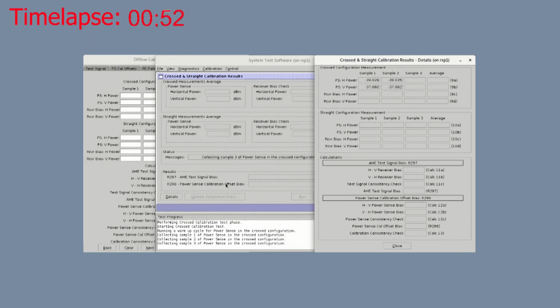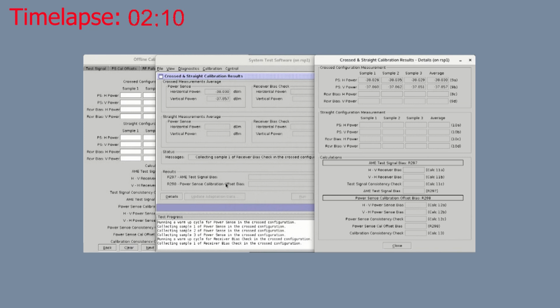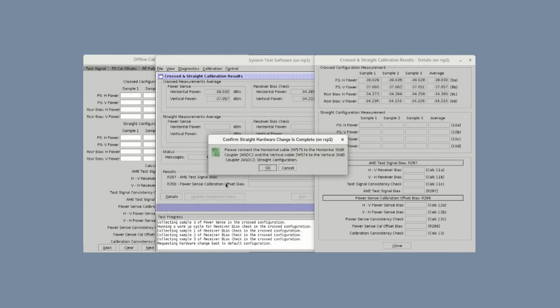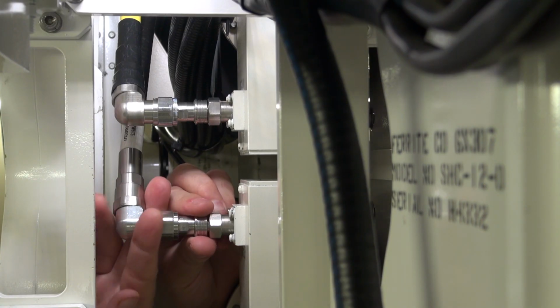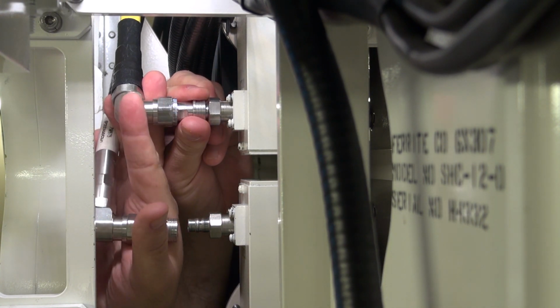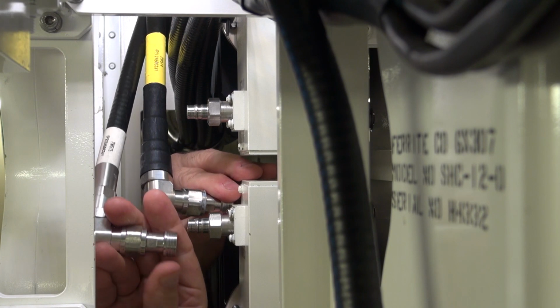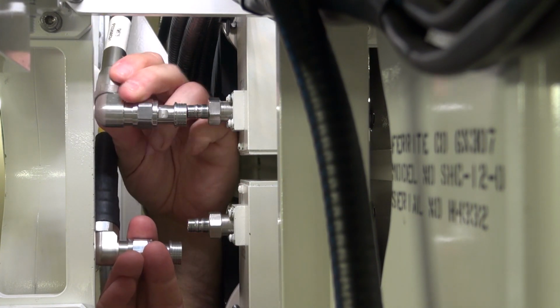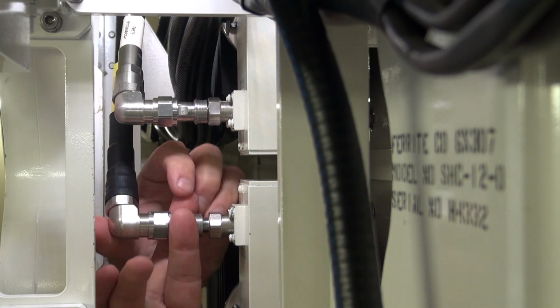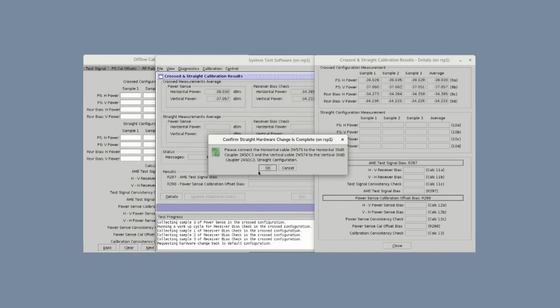Power sense measurements should be greater than -40 dB and within 0.05 dB of the previous measurement. Receiver bias measurements should be greater than -36 dB and within 0.02 dB of the previous measurement. The calibration runs for approximately 10 minutes. When it completes, a pop-up window will direct you to restore 2W575 and 2W574 cables to the straight configuration. Restore cables 2W574 and 2W575 to the straight configuration. In the pop-up window, click OK.